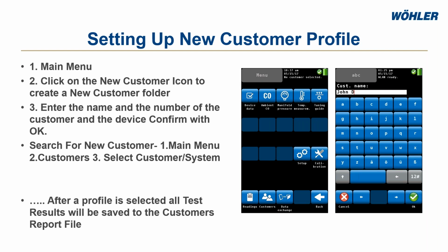So let's say we go out to a customer's job and we take an ambient CO test, we take a manifold pressure test, temperature measurement, combustion analysis test. We can put all of that within the customer profile and save that data on the analyzer. So here's just an example of how you would add in a new customer. If you're at the main screen here of the A450 or A550, you can go into customers, and once you click on customers, it's going to ask you to create a new customer. So you would hit new customer, and then you would fill out some of the details.